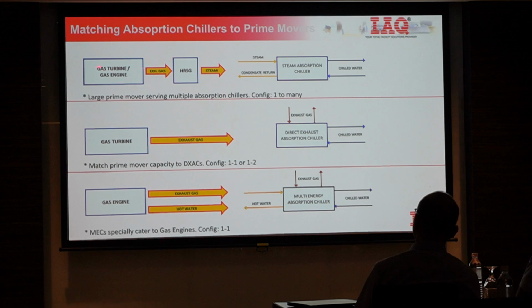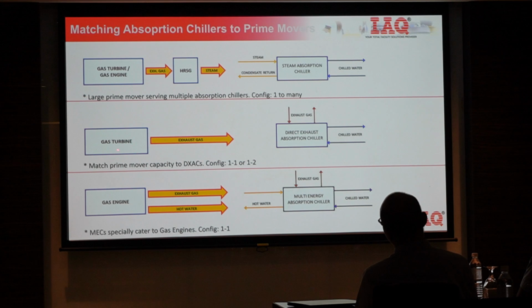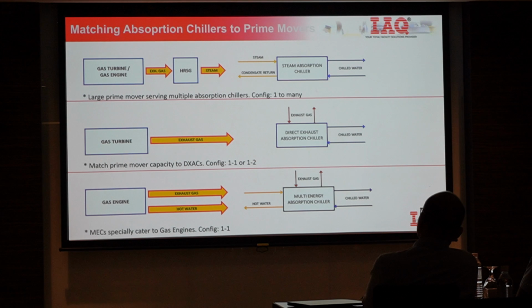So this is the conventional design with an HRSG generating steam. Second will be basically using a gas turbine, and we utilize its exhaust gas directly into a direct exhaust absorption chiller, so the flue gas will pass through the absorption chiller to generate chill water.